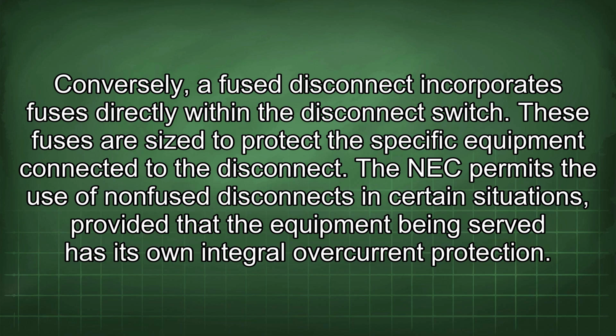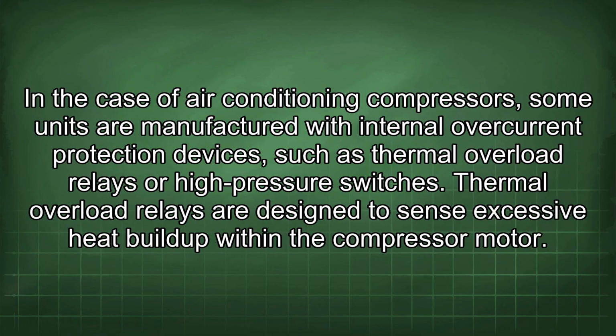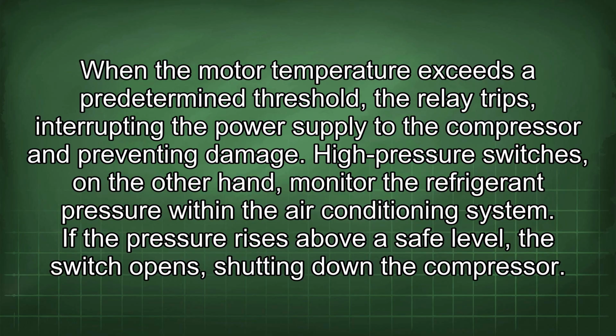The NEC permits the use of non-fused disconnects in certain situations, provided that the equipment being served has its own integral overcurrent protection. In the case of air conditioning compressors, some units are manufactured with internal overcurrent protection devices, such as thermal overload relays or high-pressure switches. Thermal overload relays are designed to sense excessive heat buildup within the compressor motor. When the motor temperature exceeds a predetermined threshold, the relay trips, interrupting the power supply to the compressor and preventing damage. High-pressure switches, on the other hand, monitor the refrigerant pressure within the air conditioning system. If the pressure rises above a safe level, the switch opens, shutting down the compressor.